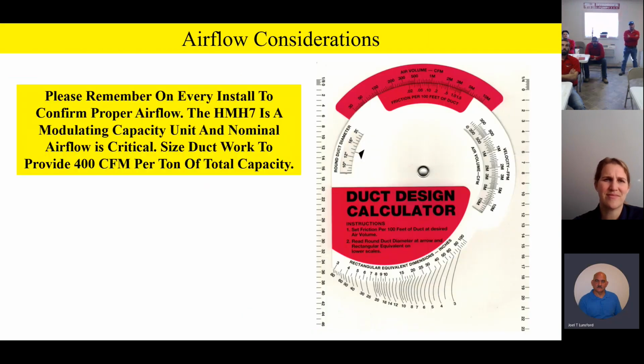Well, fellas, I just want to remind everybody, as far as airflow is concerned, remember the HMH7 is a modulating unit. So we want to make sure that we provide the proper airflow on the unit, because remember, one of the parameters of the outdoor unit is looking at suction pressure, suction line temperature, liquid line temperature, liquid line pressure, discharge line pressure, I believe, and temperature, and outdoor ambient temperature. So it's looking at all these temperatures and making intelligent decisions on where it needs to be for capacity. So if I have inadequate airflow inside, undersized ductwork, whatever, that evaporator coil is going to be cold with reduced airflow. It'll be colder than it normally would be. And the outdoor unit is going to interpret that as a reduction in capacity.